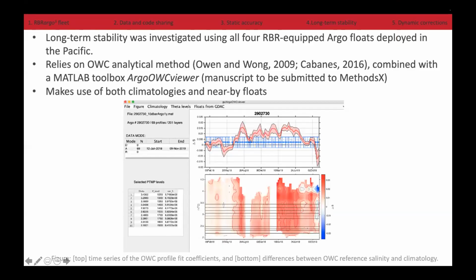Okay, so I guess the short answer is that, as Greg mentioned, we've been looking into it and characterized the drift over years, and the results are quite encouraging. I won't go into the details, but basically a few Argo floats have RBR CTDs on them, and we've been using those to assess how the instrument performs over a long period of time, like several years. There's a paper that was just submitted to JTech, and that's being reviewed right now, that basically demonstrates that the CTDs don't tend to have a significant drift. There's a very sophisticated way that was developed by the Argo community to assess whether or not the drift in salinity is important, because that's very crucial to be able to detect it and correct for it.